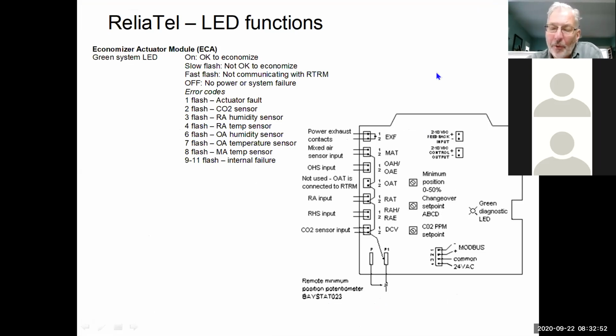On the Economizer modules that we're using today, they've got fairly good diagnostics: actuator faults, CO2 sensor. These things really do tell you what's going on. You don't have to do a ton of troubleshooting. There are some inputs and outputs on this control right here. If you're putting 2 volts in, you should get 2 volts out on your feedback output. If you're getting 10 volts in, you should get 10 volts out. In other words, these should match each other. If your input is 6 and you're only getting 2 as feedback, you've got something going on with the actuator. There's something wrong with the motor or the module. But the diagnostics are pretty self-explanatory.